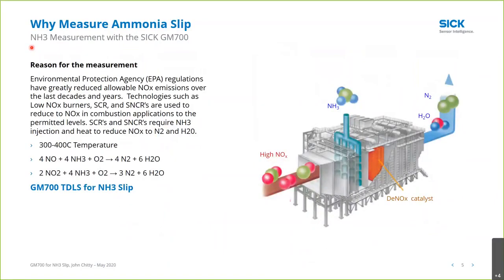So why do we measure ammonia slip? Well, the EPA regulations have greatly reduced allowable NOx emissions over the last decades and years. Technologies such as low NOx burners, SCRs, selective catalytic reduction, and SNCRs, selective non-catalytic reduction, are used to reduce NOx in combustion applications to permitted levels. SCRs require ammonia injection and heat to reduce NOx to N2 and water, nitrogen and water, through a chemical reaction. In this picture, you'll see an SCR. The catalyst bed is in this area. Flue gas comes in, ammonia is injected, and on the outlet, the NOx is reduced to nitrogen and water. Well, most of it is.